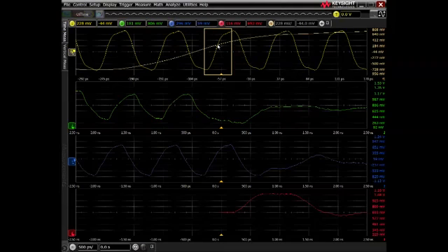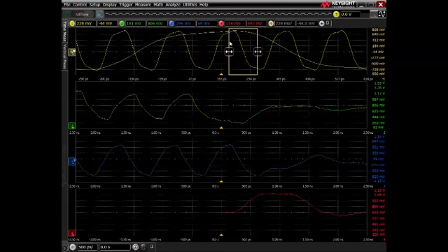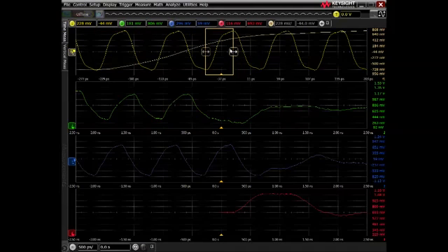The way that we perform gating within this software is you'll notice that I'm getting a secondary function. I've got this F1 function, this new waveform that's appeared, and it really is just that section of the clock that is within the gating area. So I've got this rising edge, and here's my gated rising edge. Notice as I go to a falling edge, that's what that waveform is. So I define this to the region of the clock where I want to make my measurements.